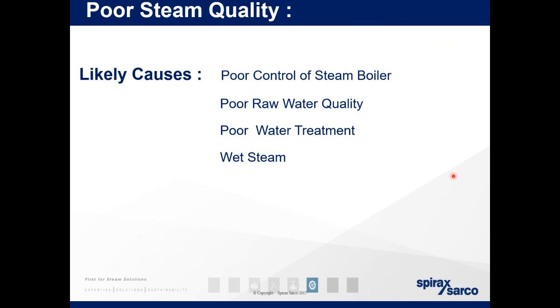And wet steam, so from bad insulation, from poor quality steam, wet steam will introduce water into your lines. Water has a lower enthalpy than steam, so it's giving out less heat, which makes your system less efficient.